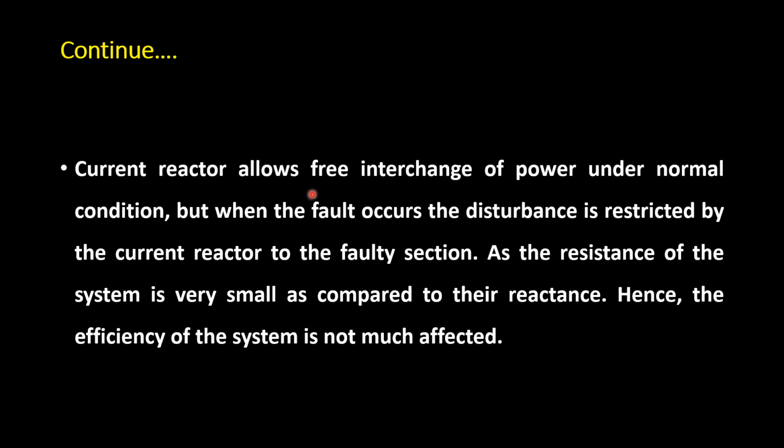Current limiting reactors allow free interchange of power under normal conditions, but when a fault occurs, the disturbance is restricted by the reactor to the faulty sections. As the resistance of the system is very small as compared to its reactance, the efficiency of the system is not much affected just by inserting additional reactance in the power system.